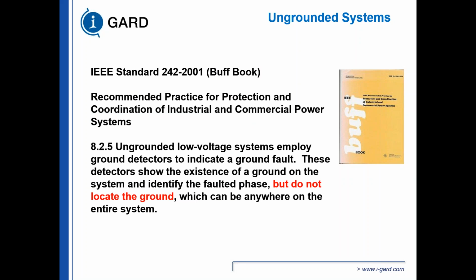So the Buff Book says that ungrounded low voltage systems employ ground detectors to indicate the presence of a ground fault. And again, we described that the ground detectors are bulbs, or if you have a high potential ungrounded system at 5 kV, you have to have grounding PTs, and then you load the secondary of the PTs. So basically what you're doing is measuring the voltage with respect to ground. If you have a ground fault, one of the bulbs is going to go out. These detectors show the existence of a ground fault, but do not locate the ground fault. It is very, very difficult to locate a ground fault in an ungrounded system.